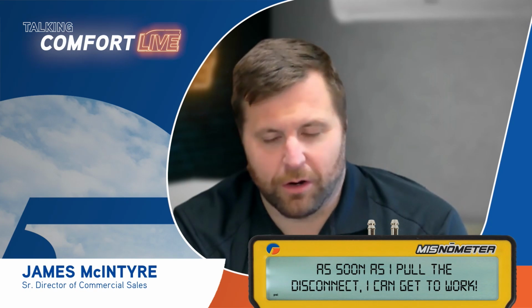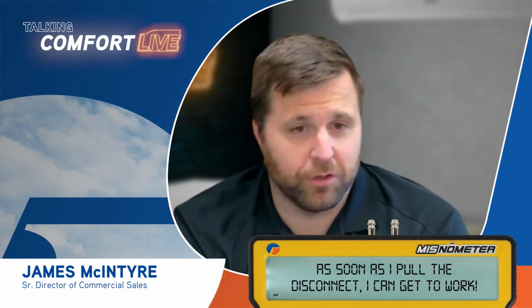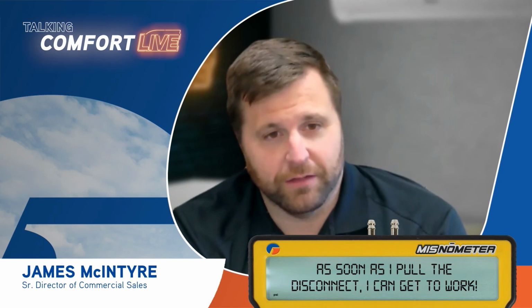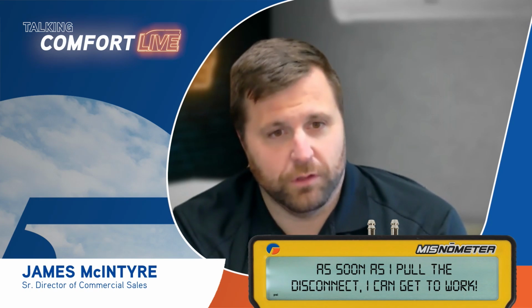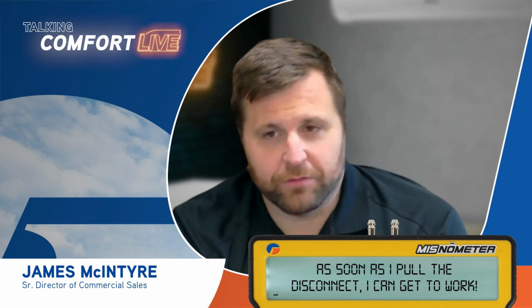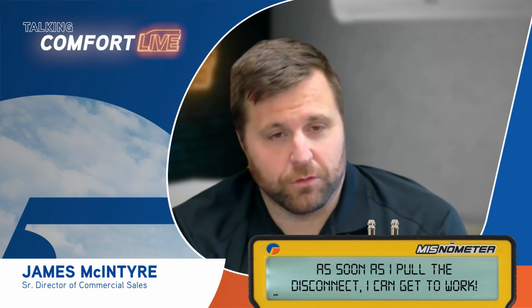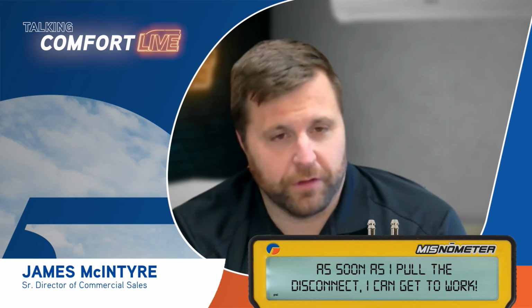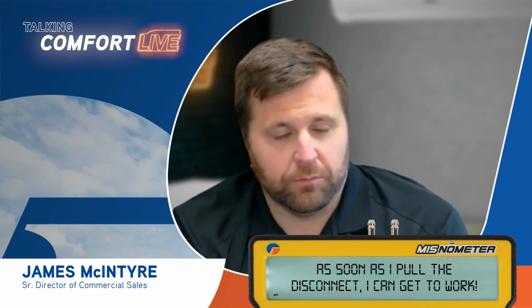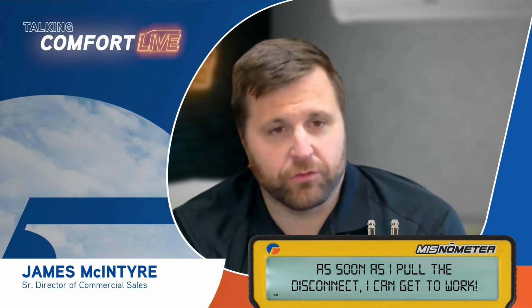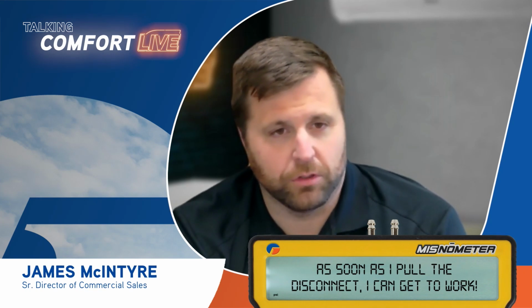Our capacitors, we've got capacitors just like every other piece of equipment's got capacitors. They can take some time to discharge. Those capacitors are built onto the board for the most part. There are test points for those. On every single one of our inverter boards, you can measure that voltage, and after that voltage has dissipated, you can get to work.